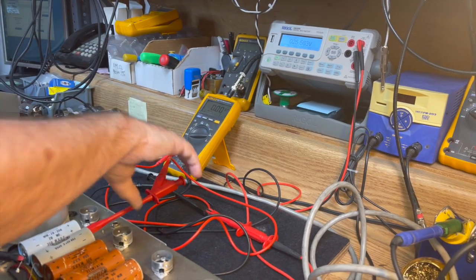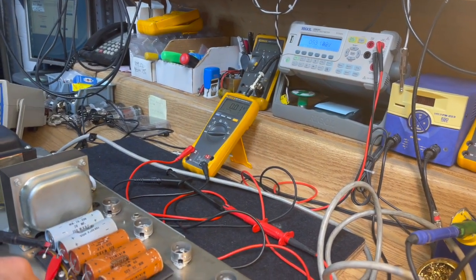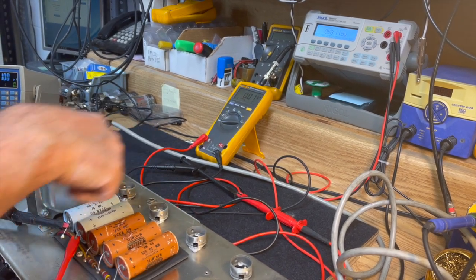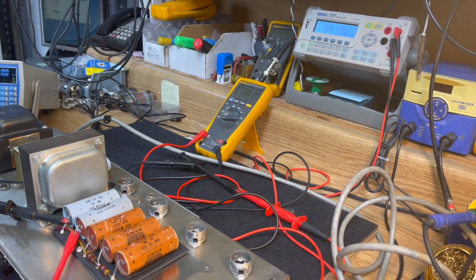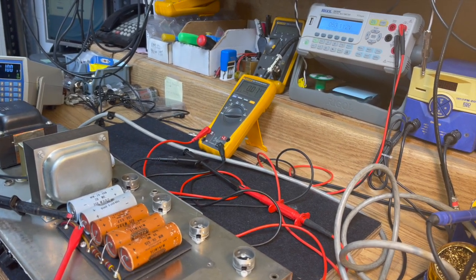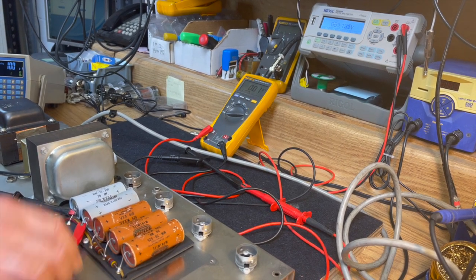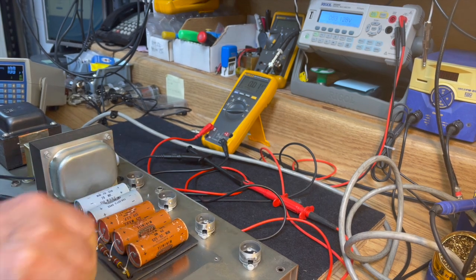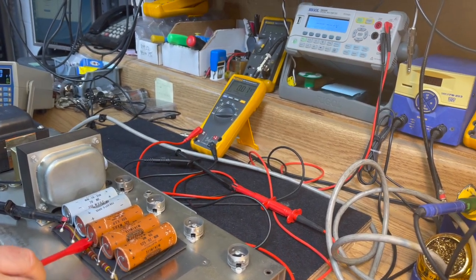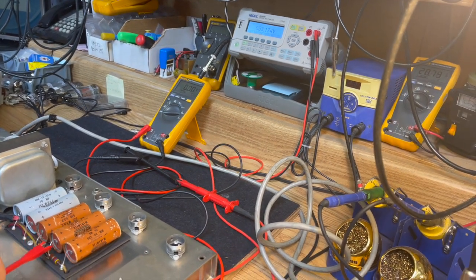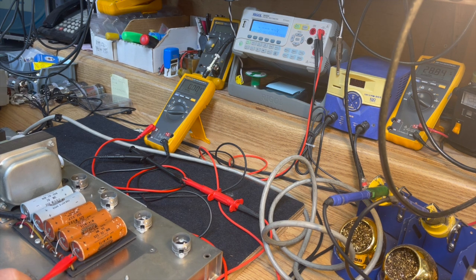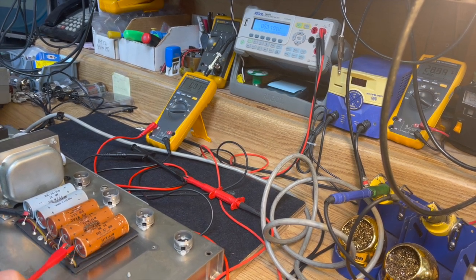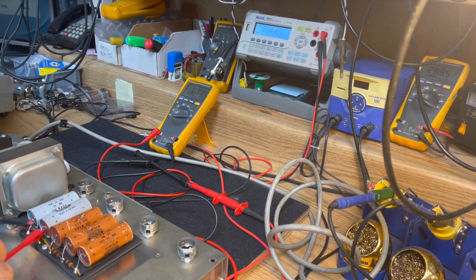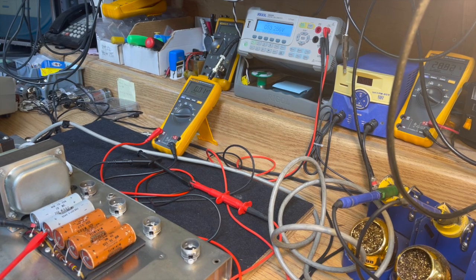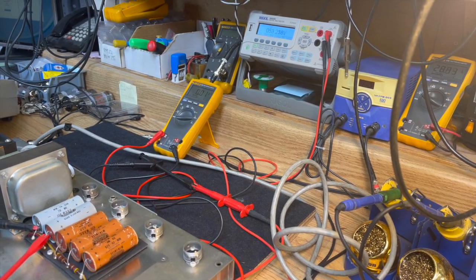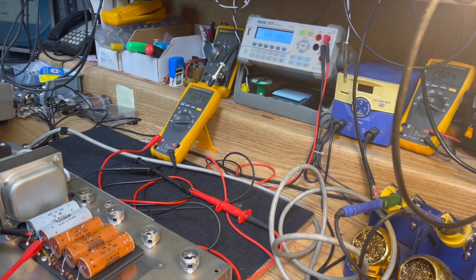But we were at 53 volts and halfway, and at the halfway point we're reading 25 and a half. So again, everything is looking really good and there's no current draw. So I think that under the circumstances, now that we're up at 50, we've still got a milliamp there, still got a milliamp there, still got a milliamp there. So we don't have any concerns right now, and we don't have enough current being dissipated by the capacitors to indicate that the electrolyte is going to overheat.